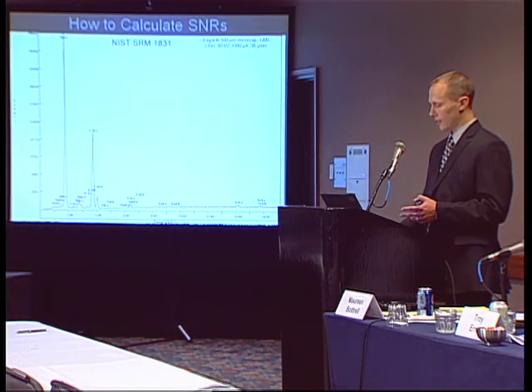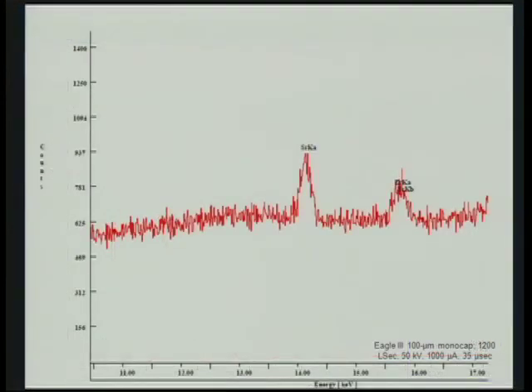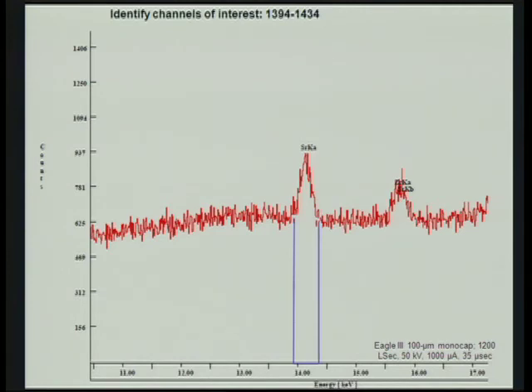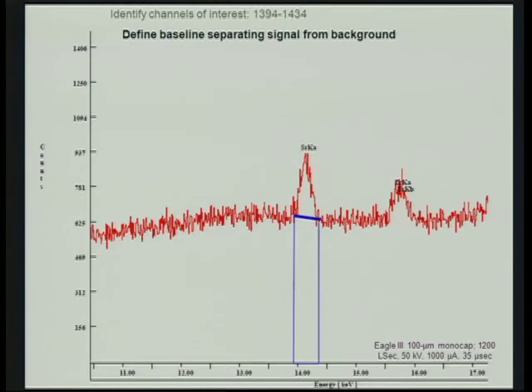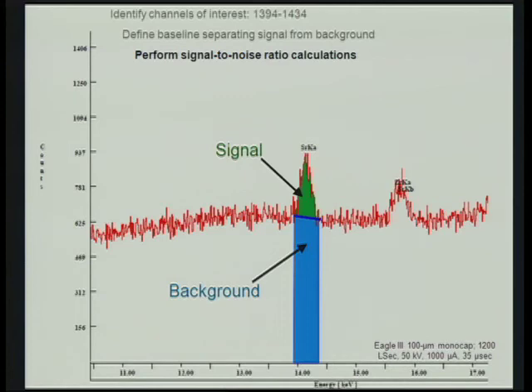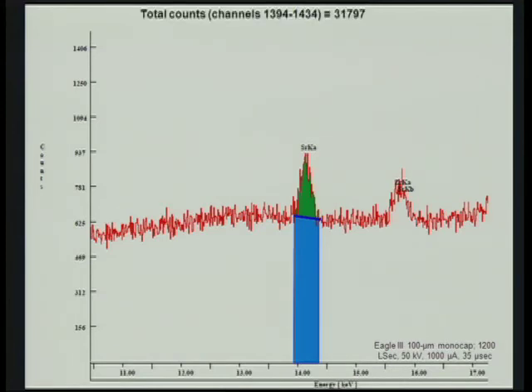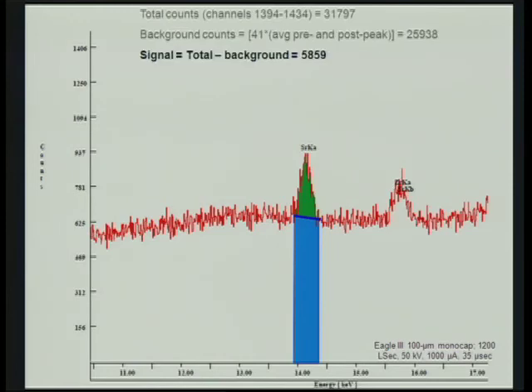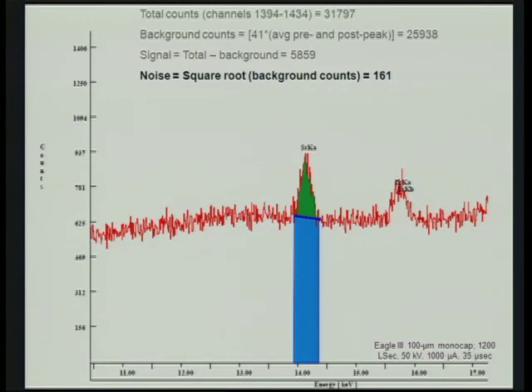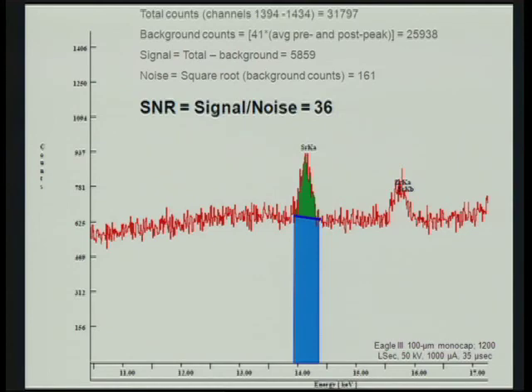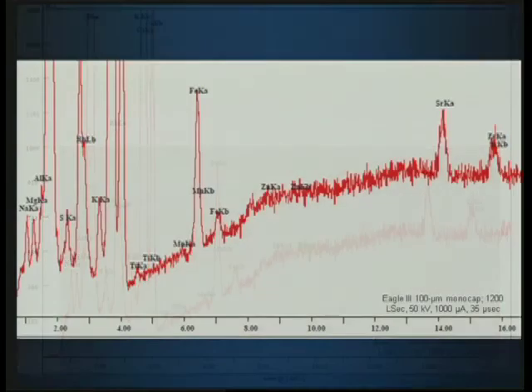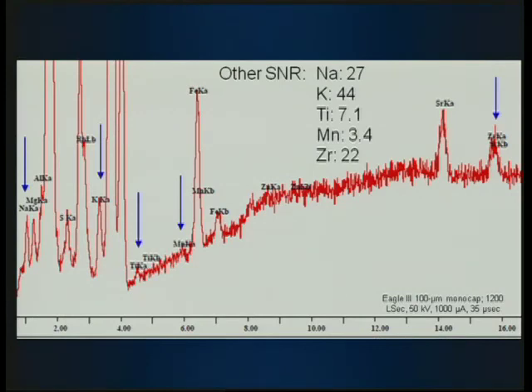Here's how those ratios are calculated. I have a spreadsheet set up where it's a cut-and-paste, and within seconds you get all the signal-to-noise ratios for each element in that spectrum — so it's not a tedious hands-on process. Here's SRM 1831, using strontium as an example. First, identify the channels of interest. Next, define the baseline that separates signal from background. Then perform your calculations: total counts through those channels, background counts, the signal is total minus background, and the noise is the square root of the background counts. The signal-to-noise ratio for this strontium peak is 36. Calculated across the spectrum, all of these results come out in a matter of seconds.